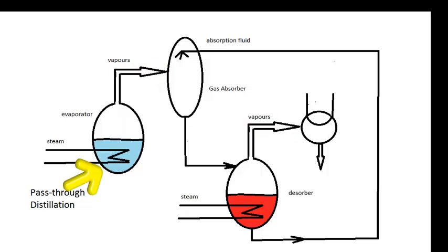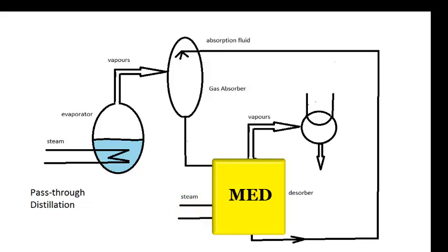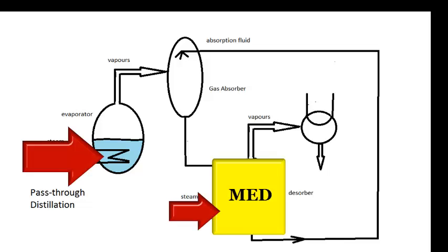In the first evaporator, it came from a fussy, temperature-sensitive fluid or slurry, for which multiple effect distillation was unsuitable. But the second distillation involves clean, thermally stable fluid, to which multiple effect distillation is readily applied. Using three effects, the plant steam required for the absorption fluid regeneration is roughly half that required at the front end.